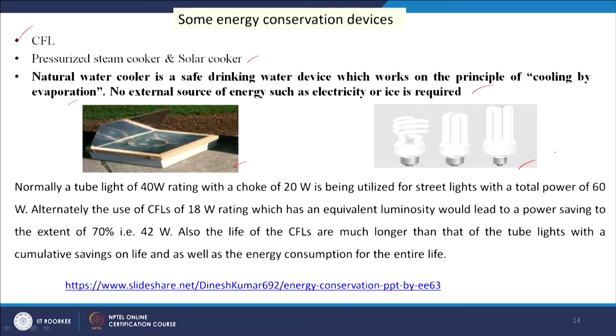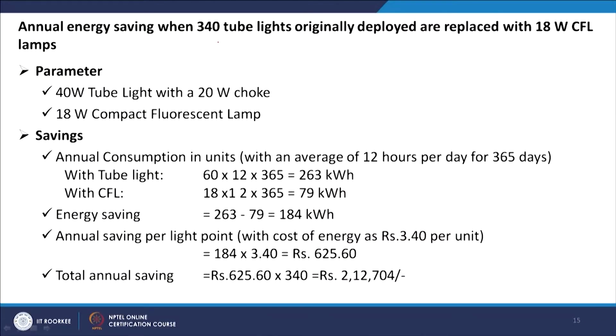It has been shown that a tube light of 40 watt with a choke of 20 watt, that is a total of 60 watt, gives the same amount of luminosity as a CFL of 18 watt. So, there is a 60 minus 18, 42 watt, or 70% saving in electricity. Now, here are some calculations. The annual energy saving when 340 tube lights originally deployed are replaced with 18 watt CFL lamps. So, 40 watt tube lights with 20 watt choke and an 18 watt compact fluorescent lamp, CFL, that we have just discussed. So, what will be the saving?